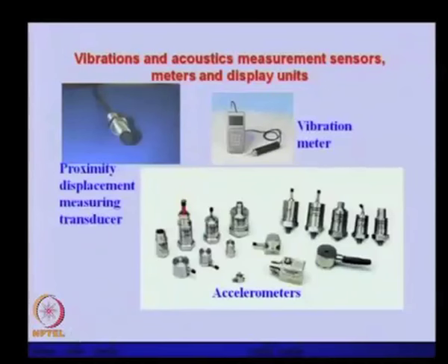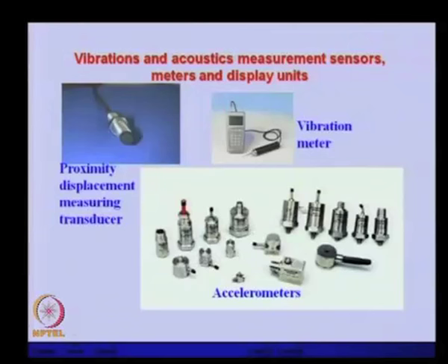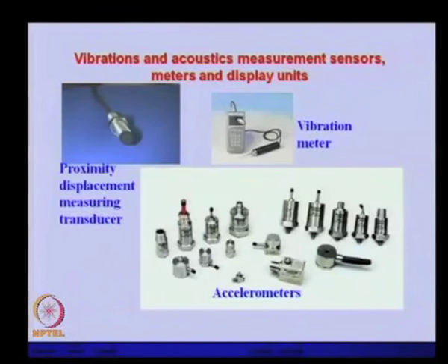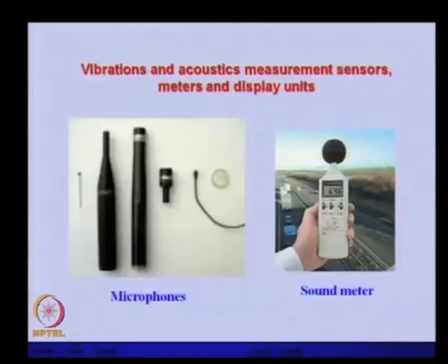To collect this data we have various kinds of sensors. One is the displacement-measuring proximity probe. There are also varieties of accelerometers — piezoelectric-based accelerometers — which give a voltage signal proportional to the acceleration of the body on which they are mounted. Various mounting options are available, such as base-threaded bolts or adhesive. A hand-held vibration meter can provide simple RMS values or vibration level information.